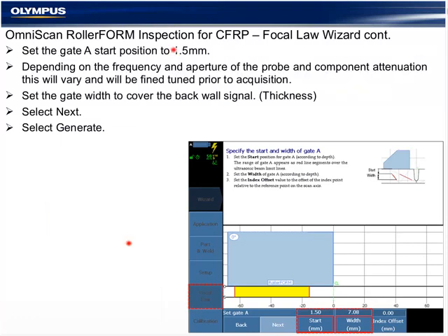At the end of the focal law wizard, the software gives us the opportunity to set our gate A to shortcut some of our setup. It has nothing to do with the actual focal law creation. A good starting point would be about 1 to 2 millimeters. We want the gate as close to the interface signal as possible, and we need enough width to include the gate A, the red gate A, all the way over the back wall. We'll fine-tune this once we get into inspection preparation. Select Next.